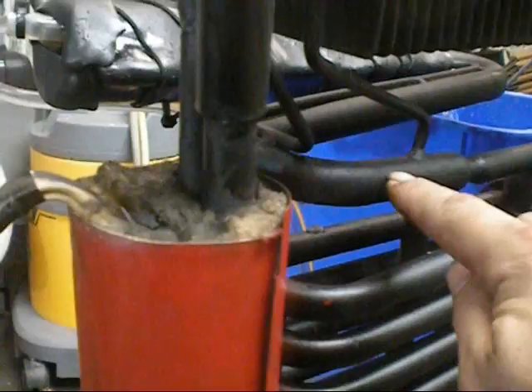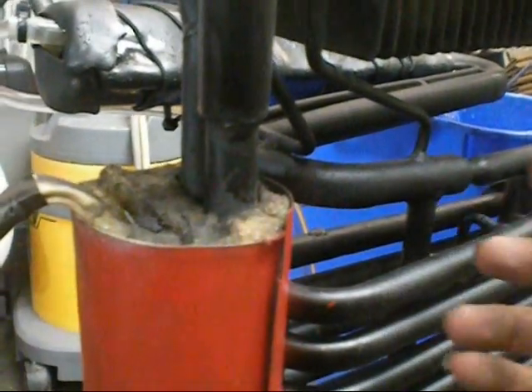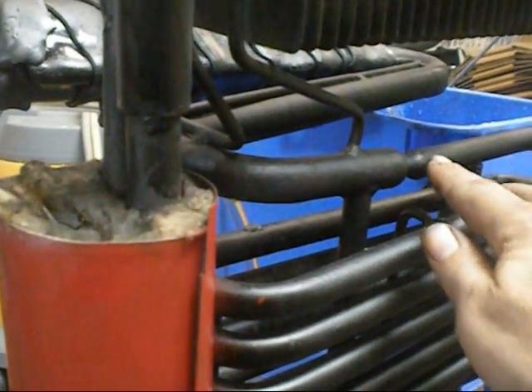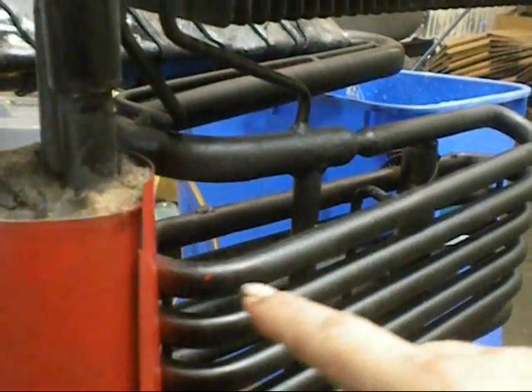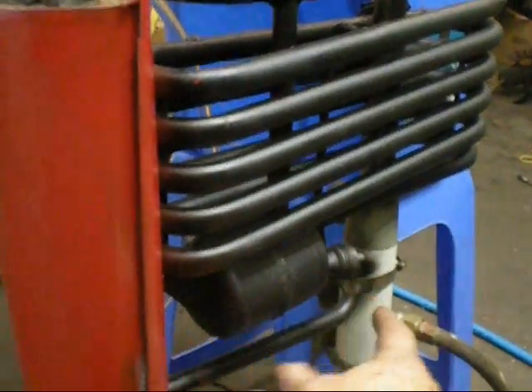It comes down the evaporator tube as an evaporated gas again, then down here into the absorber, which absorbs the gas back into the water. Then there's your solution tank, and it goes back into the generator.